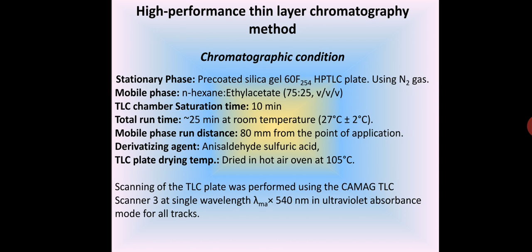The total run time is around 25 minutes at a room temperature of 27 degrees Celsius, and we have run the mobile phase on the TLC plate up to a height of 80 millimeter or 8 centimeter from the point of application of the sample spot. The visualizing reagent we have used here is anisaldehyde sulfuric acid reagent, which was sprayed on the developed HPTLC plate, and the plate after spraying the reagent was dried in a hot air oven at 105 degrees Celsius for 10 minutes. Under these ideal conditions, you can obtain reproducible results using this HPTLC method.